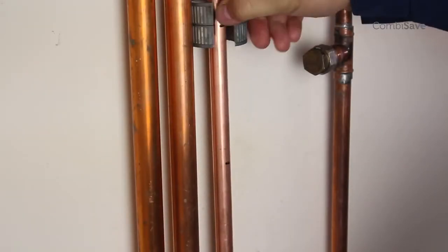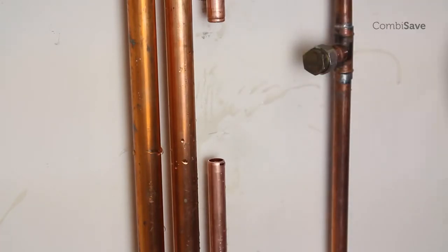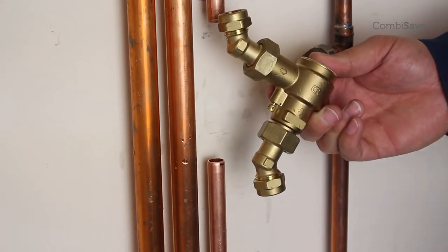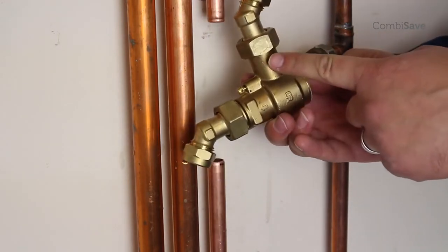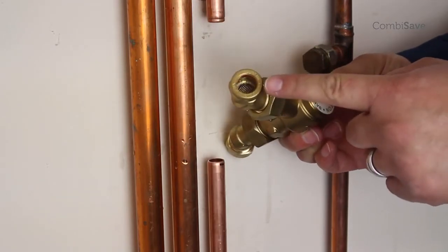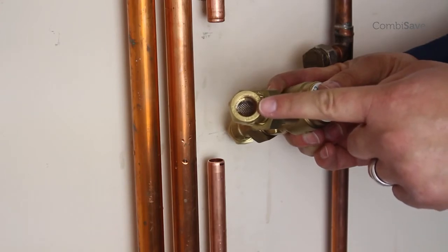Using a pipe cutter, remove the appropriate pipe section and ensure that there are no burrs or sharp edges. When fitting the CombiSave, make sure that you fit it the right way around. The direction of water flow is indicated on the outside of the CombiSave body. Also, it is worth noting that the elbow for the inlet to the CombiSave has a gauze filter, designed to reduce the debris entering the CombiSave.